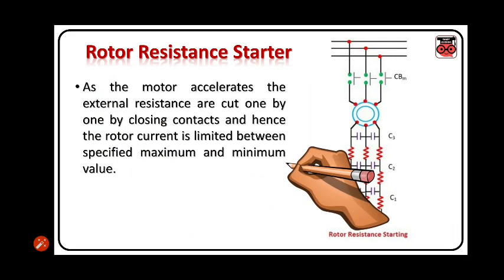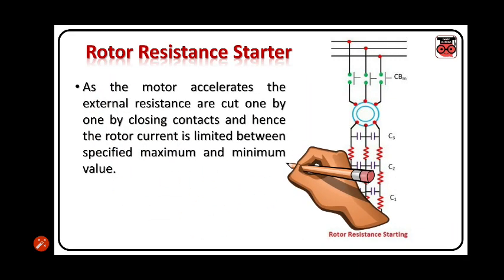As the motor accelerates, the external resistances are cut one by one by closing contacts and hence the rotor current is limited between specified maximum and minimum values.